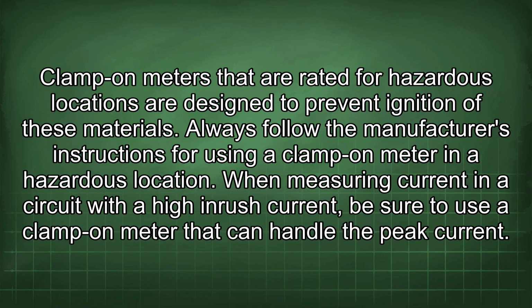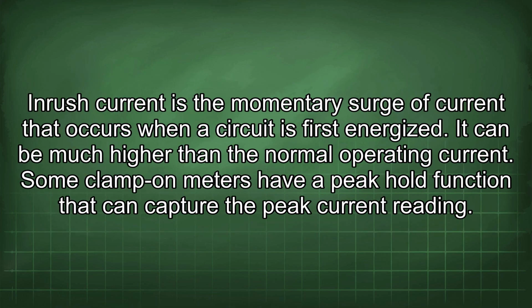When measuring current in a circuit with a high inrush current, be sure to use a clamp-on meter that can handle the peak current. Inrush current is the momentary surge of current that occurs when a circuit is first energized. It can be much higher than the normal operating current. Some clamp-on meters have a peak hold function that can capture the peak current reading.